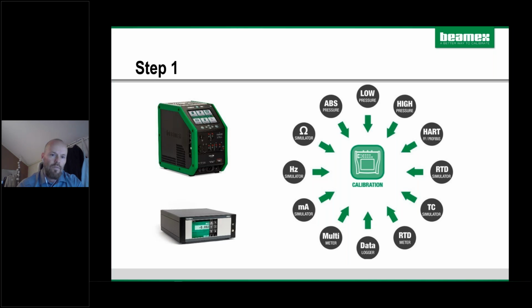You can also have the same communication with temperature blocks. Here again, the calibrator communicates with the temperature block and sets the desired temperature as you go up through the calibration points, from 0% to 50% and up to 100% and down again. The calibrator will communicate that and do it for you.